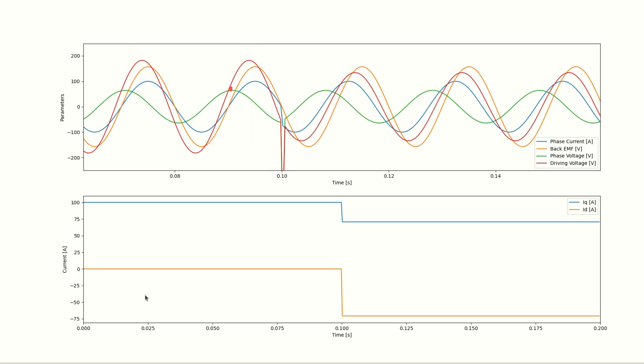Notice that the phase difference between the phase voltage and the phase current hasn't changed. That phase difference is a function of the speed and the motor parameters, specifically its resistance and inductance, and we can't change those.